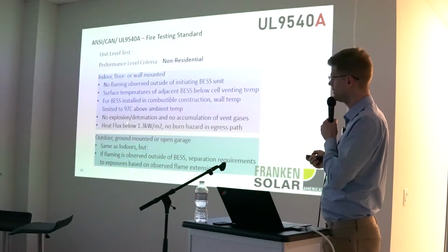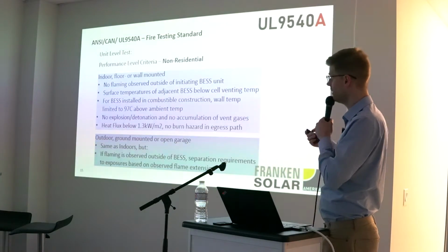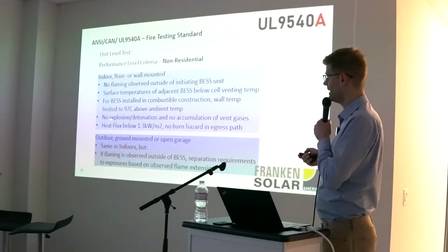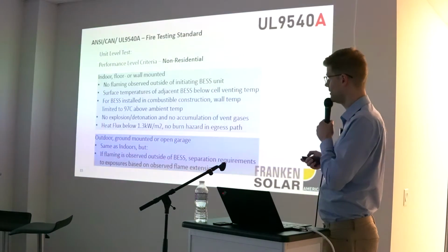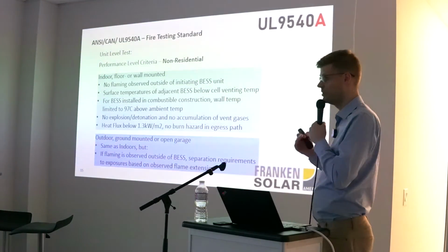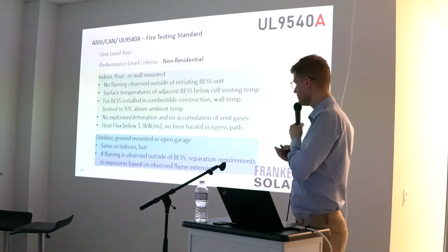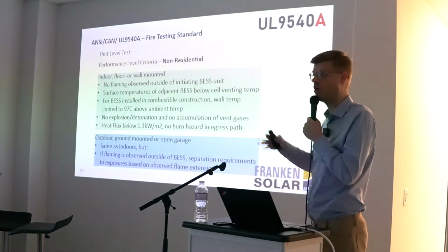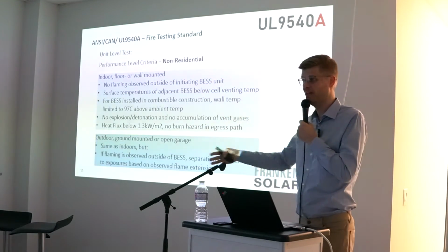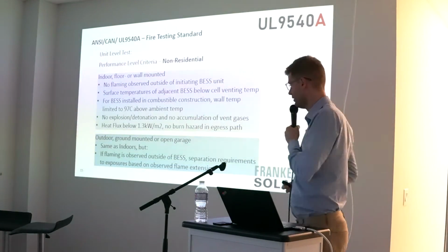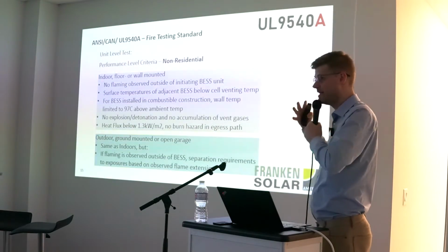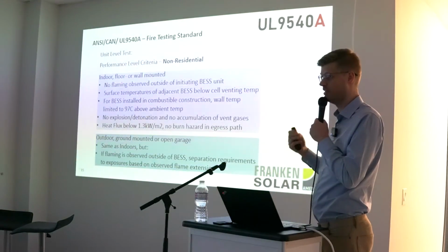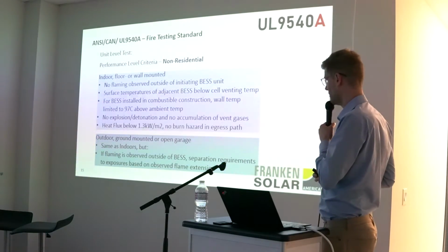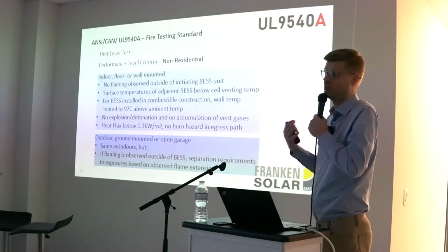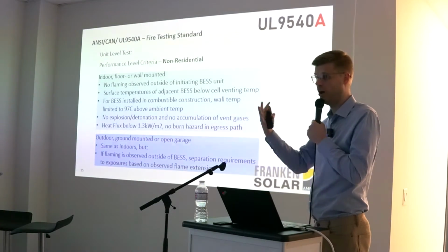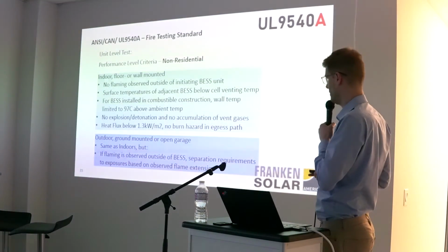Non-residential is pretty much the same as what we already saw on the residential, but in addition there is another level: the heat flux, so the radiated heat into an egress path. If there's a walkway, for example, to an emergency exit, and a person walks through that walkway, the radiation and the heat to that person cannot exceed a certain radiation level, in this case 1.3 kilowatts per square meter, so that the person would not get burned by that very hot system he or she is walking past.